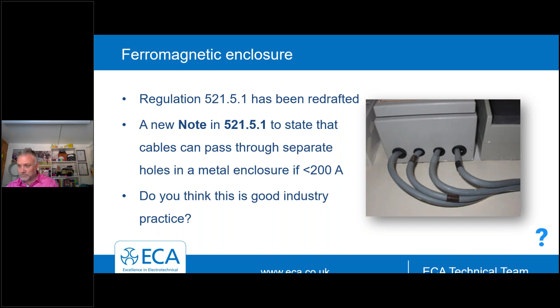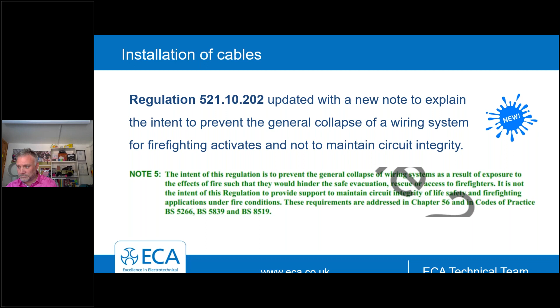Something that has been clarified is the installation of cables in escape routes. There is a new note to clarify the intent of the regulation is to support the cables and not hinder firefighting activities. It also notes that circuit integrity, i.e. keeping the service running, is addressed in chapter 56, and that's handled by other British Standards like 5266, 5839 and 8519, so life safety systems. So again, it's keeping the cable supported, not hindering firefighting activities, but it's not there to keep the service running. That's the job of other British Standards.